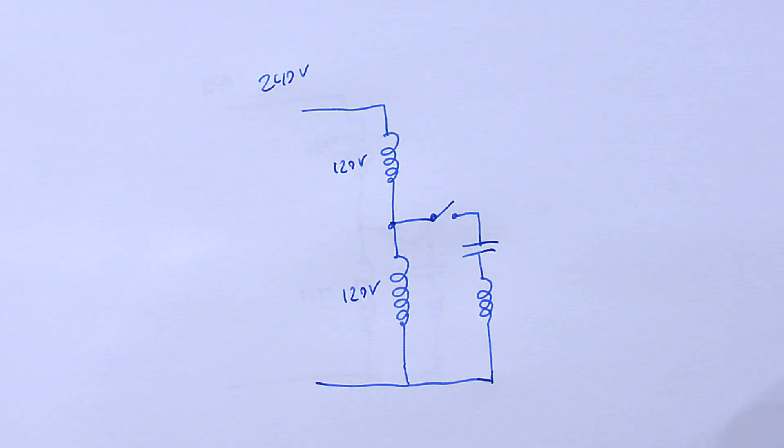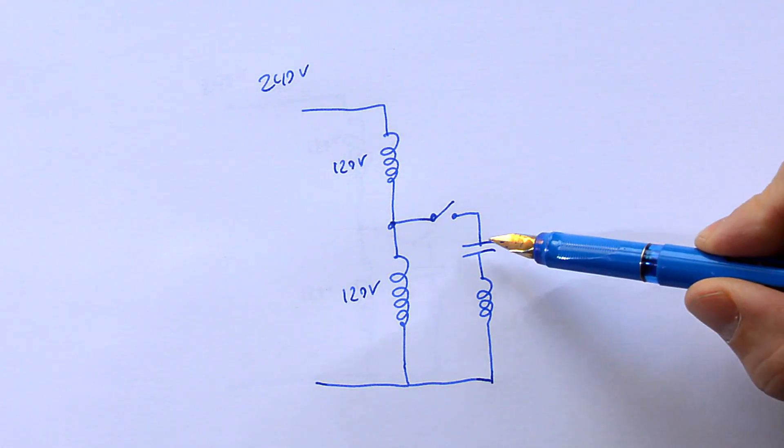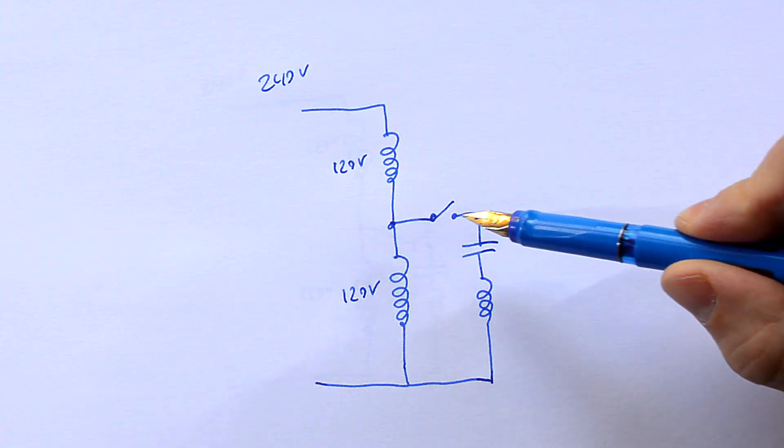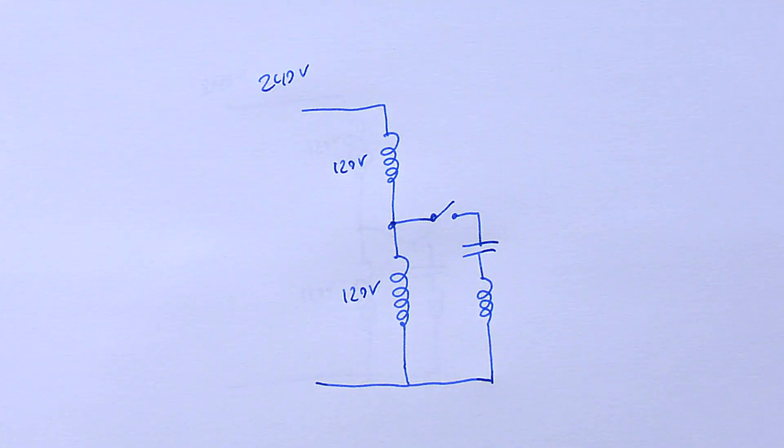But it's actually more complicated than that because this is a single phase induction motor and it has a starter winding in series with a starting capacitor and a starting switch and that is only turned on when the motor is starting.